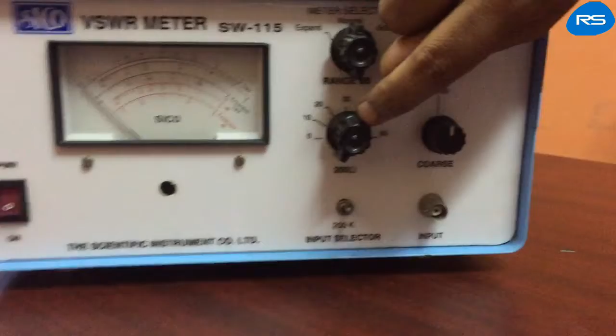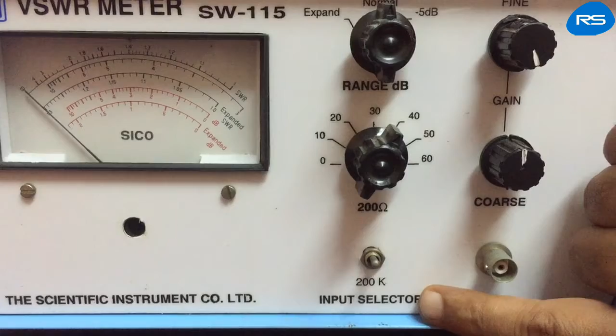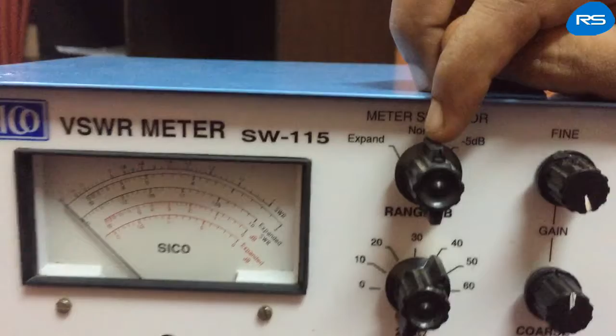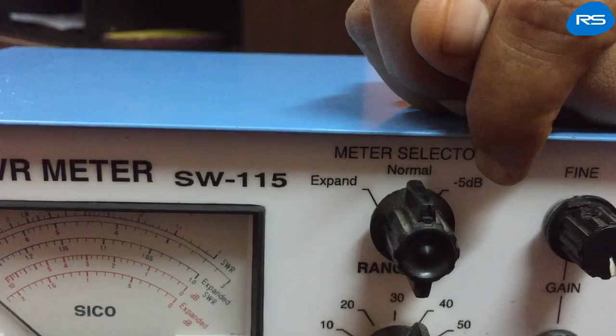This is the range switch. It is a 7-position attenuator, minimum in 10 dB steps. This is a crystal switch. It is an input selector switch for low and high inputs, that is, high 200 kilo ohms crystal and low 200 ohms. This is your meter selector switch. This is a 3-position switch: normal, selection for normal scale, expand, selection for expanded scale, and -5 dB scale.